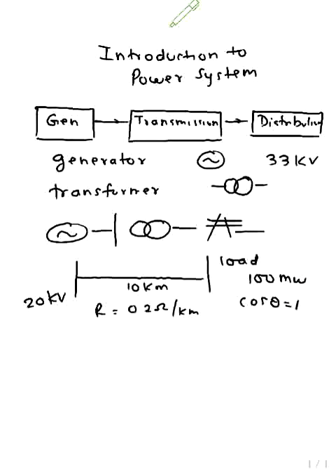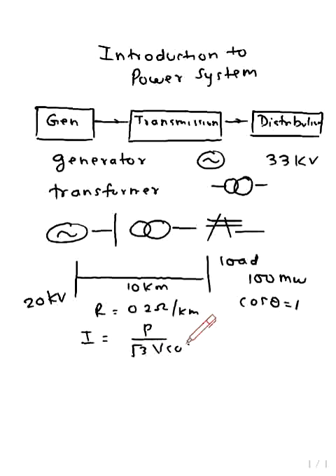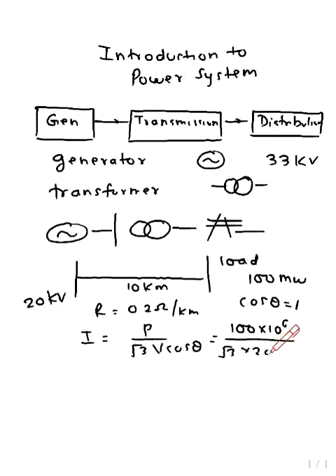We find the current in the transmission line using I = P / (√3 × V × cos θ). Substituting P = 100 MW and V = 20 kV, we calculate the current to be 2886.75 amperes. This is too much current.